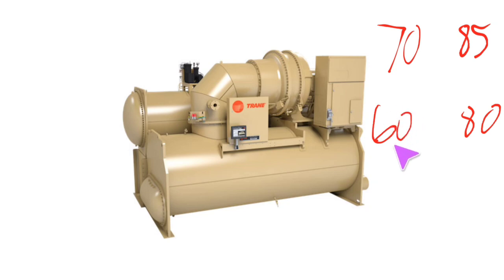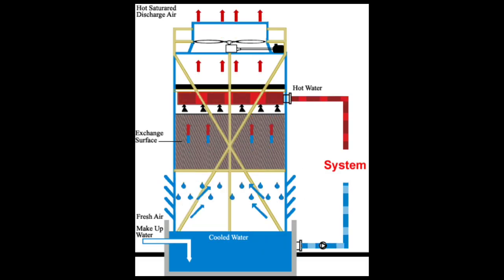I try not to run more than 80 degrees on those, but I can run down as low as 60 degrees on their condenser water because they handle low lift very, very well, and this can get a lot of extra efficiency. Those are just some rule of thumb ranges I gave you. I didn't just give one set temperature that I wanted to stick with. It wasn't just 70 or 75, and that's because I really recommend not going that direction. If a plant is set up properly and is commissioned properly, you're not going to have just a static set reading when it comes to your condenser water.